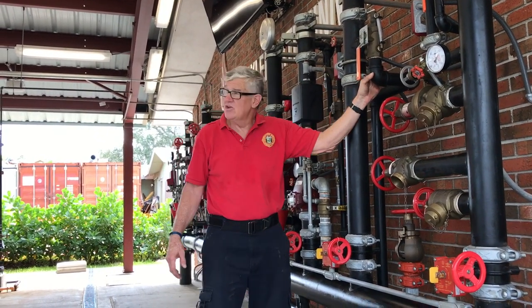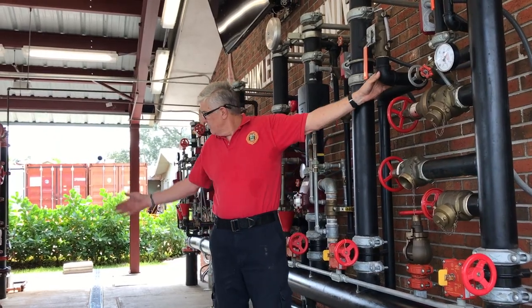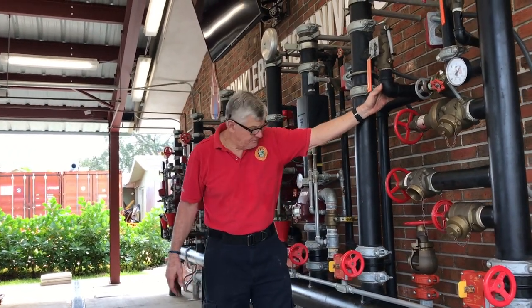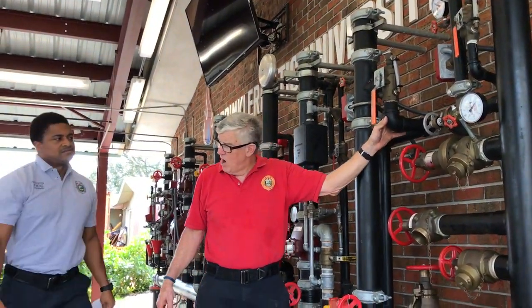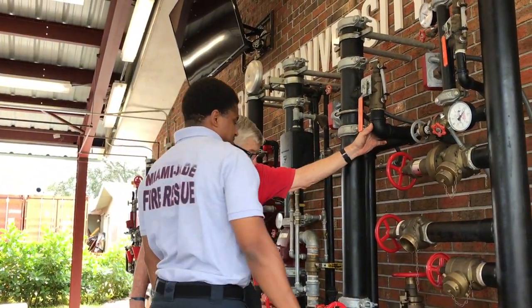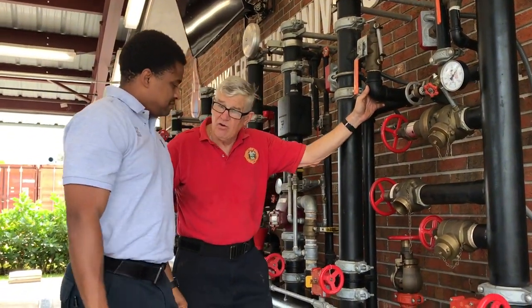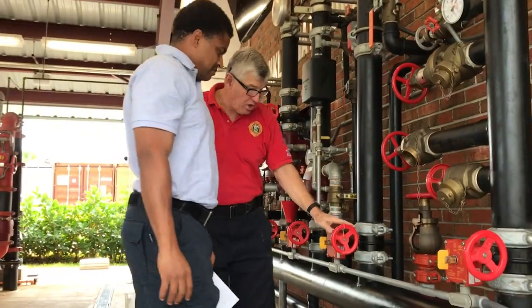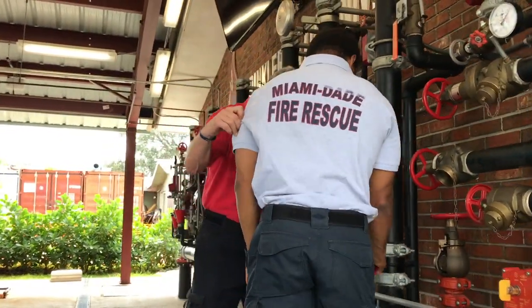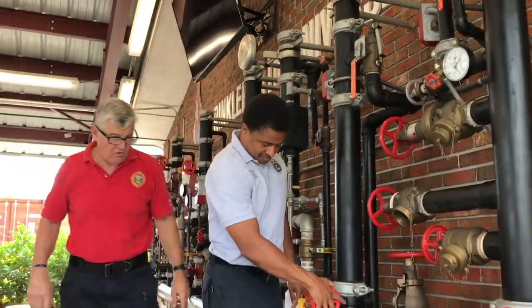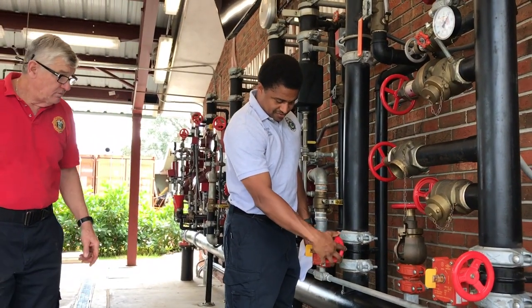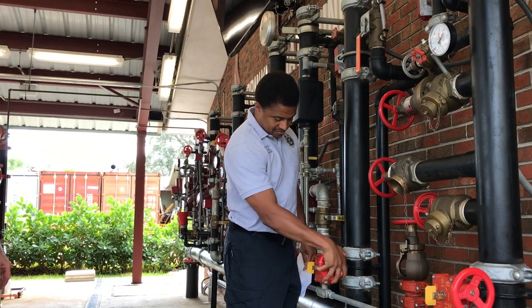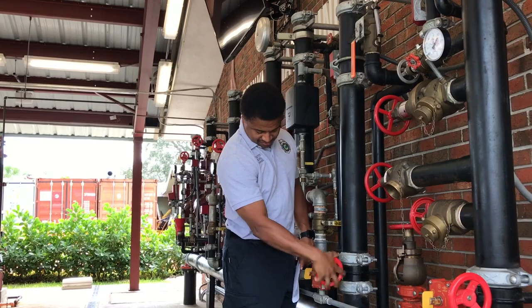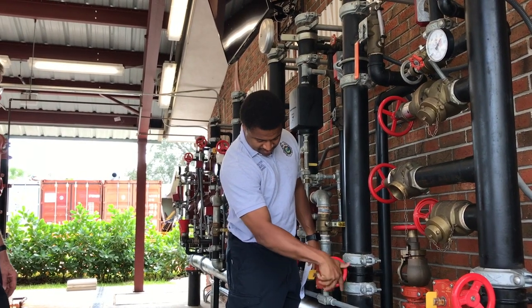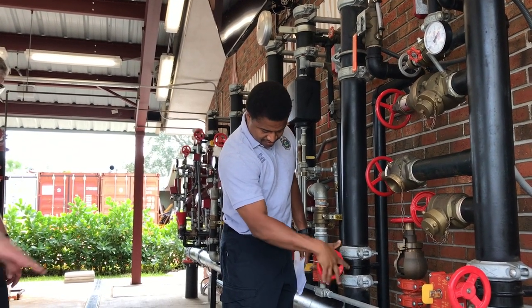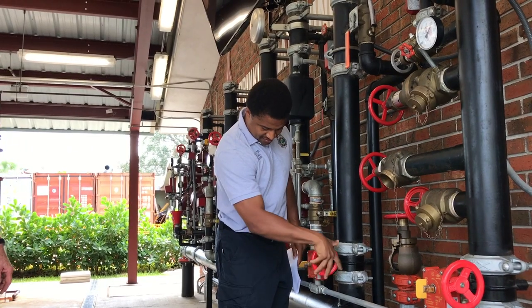So in this case, come on up, Mark. We've got a water flow. We've determined that the fire is either out or it's a broken water pipe. We're gonna go ahead and close the control valve. Come on over here. Close the control valve. Okay, and we can see that we're shutting it off because of the indicator.